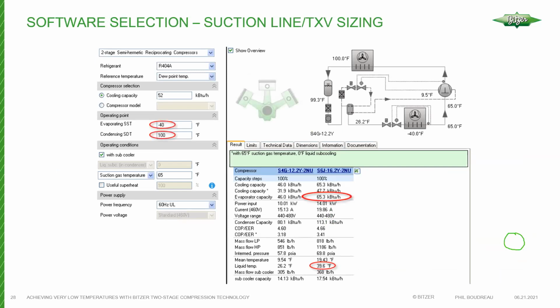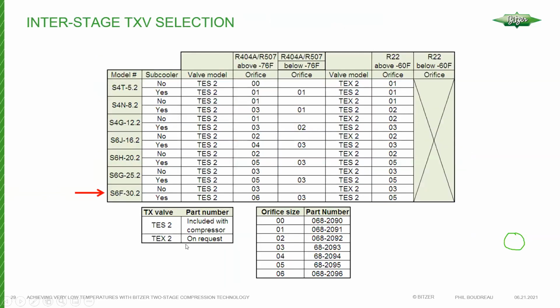So when sizing for your suction line and your expansion valve, we need to consider the capacity of 65.3. This is your evaporator capacity. Okay, and we've got 39.6 degree Fahrenheit liquid, and we're operating at -40 Fahrenheit saturated suction temperature, and we've got a saturated discharge temperature of 100 degrees.